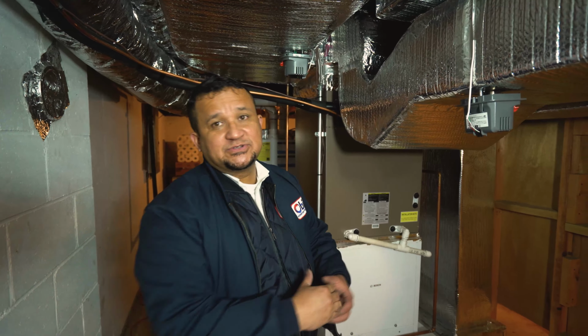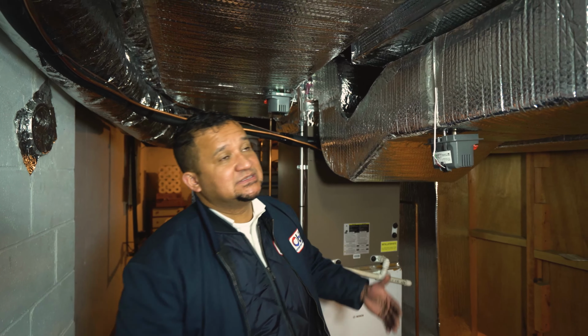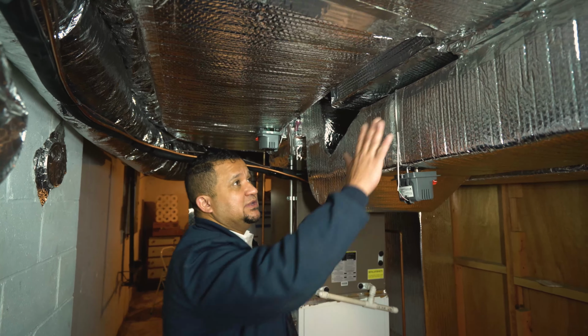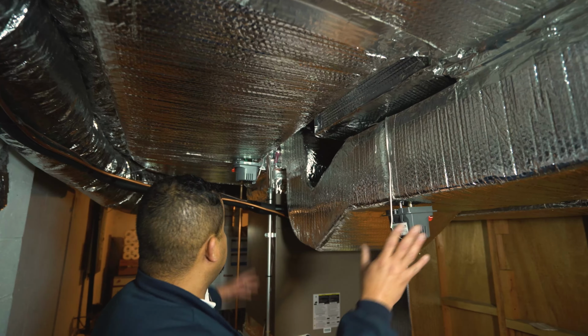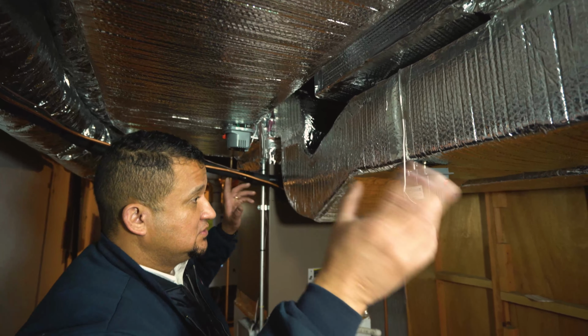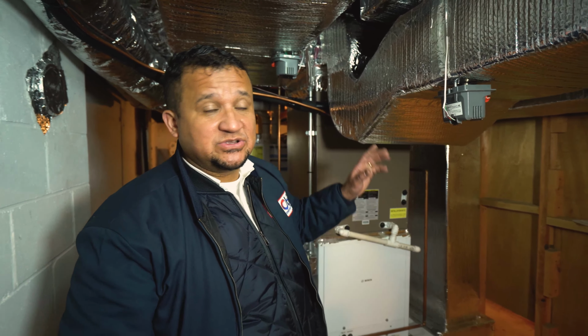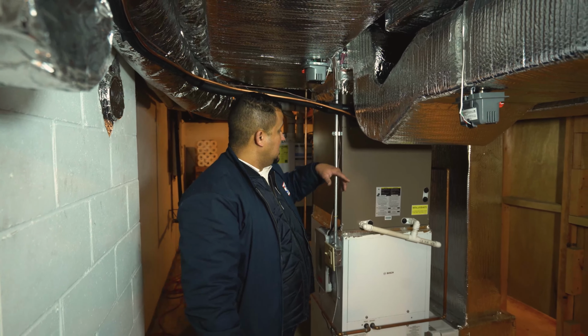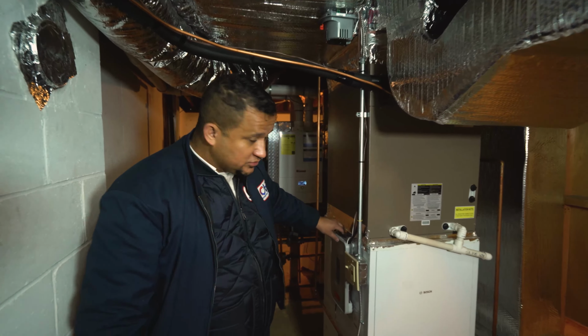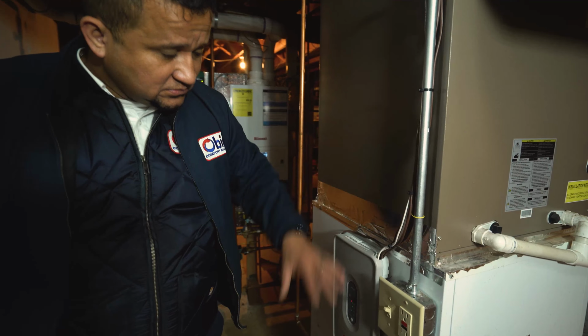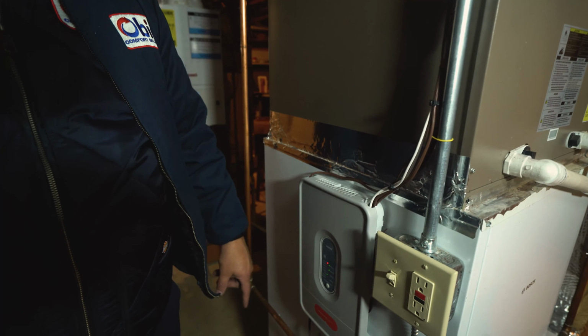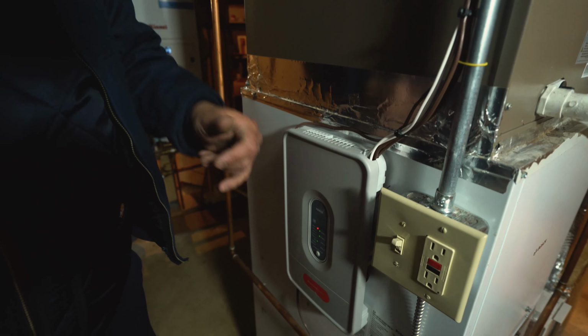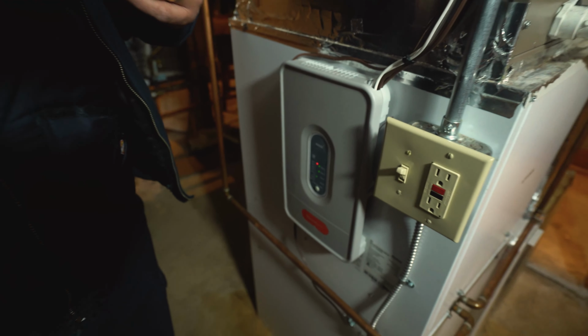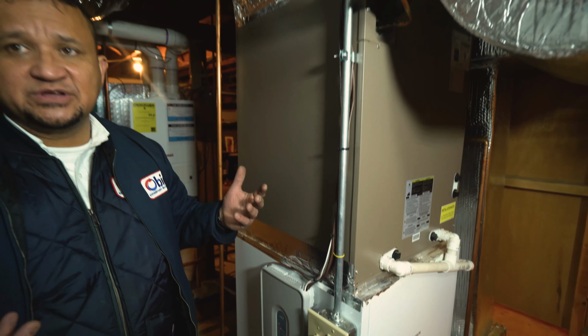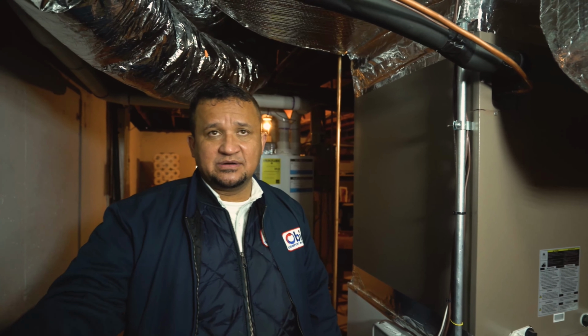So guys, this is a wrap, the whole job is complete. Some of the stuff you see in here: we insulated the ductwork, we installed the zone dampers, so now there are going to be two lines. We installed a separate thermostat that was not installed in the other zone. We connected the zone control board. This is the proper one with an outdoor sensor, so we set it for 32. Below 32 degrees, it's going to switch to propane, but as long as the temperature is above 32 degrees, it's going to use the heat pump as a source of heat.